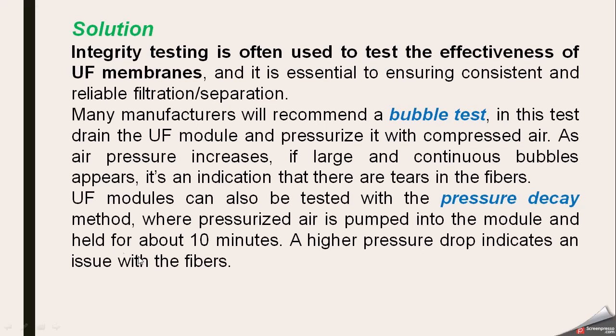Very simple. In the second type of test, which is pressure decay, pressurized air is pumped into the module and held for about 10 minutes. If a higher pressure drop occurs, then this is an indication that there are some issues with the fibers or there are tears in the fiber. So these two types of tests are applied to check the integrity of the membranes.